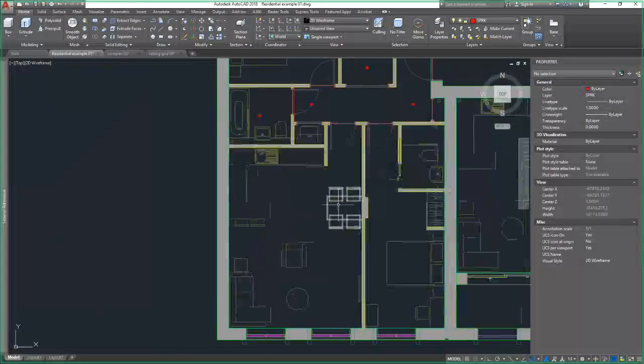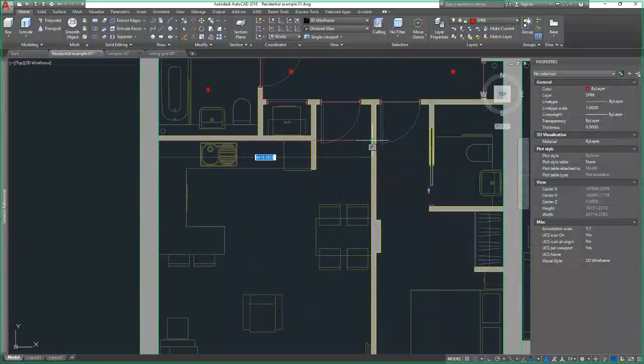Right, let's have a look at this living space now, because we get into a bit of a larger area. We've got a little bit of space over by the doorway, and then we've got this kitchen, dining, lounge area. So let's have a look at this distance first. That's 6.2 meters. If I do 6.2 divided by 4, we get 1.55. So it's definitely going to be 2 sprinkler heads down this row here. What about the width? The width is 4.